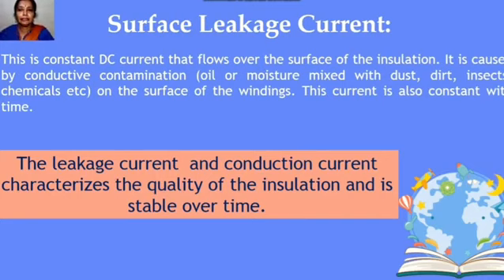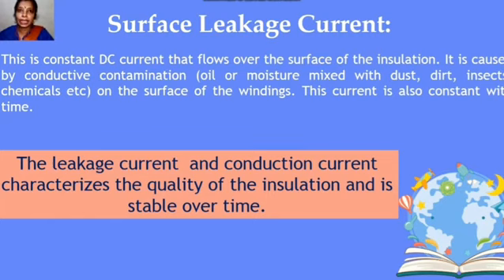The surface leakage current is a constant DC current that flows over the surface of the insulation. It is mainly caused by conductive contamination — oil or moisture mixed with dust, dirt, insects, or chemicals on the surface of the windings. This current is also constant with time. The leakage current and conduction current together characterize the quality of the insulation. In some literature, both conduction and surface leakage current are combined and called the leakage current component.